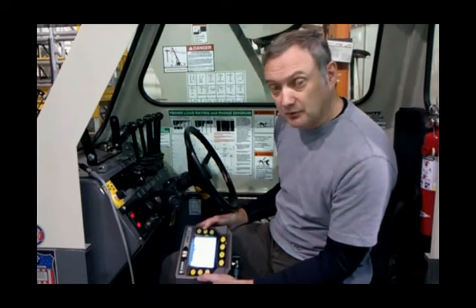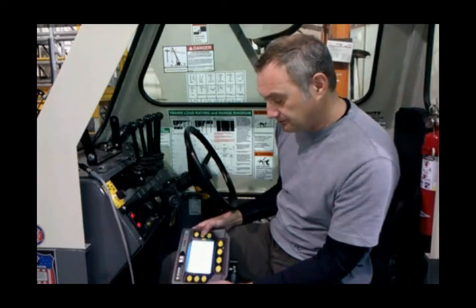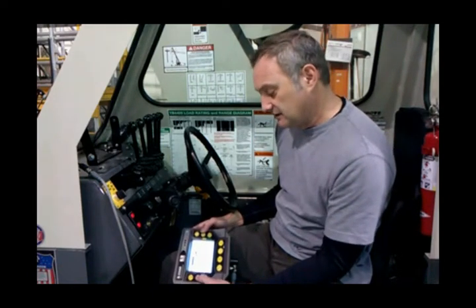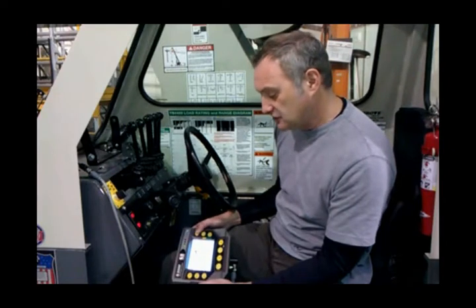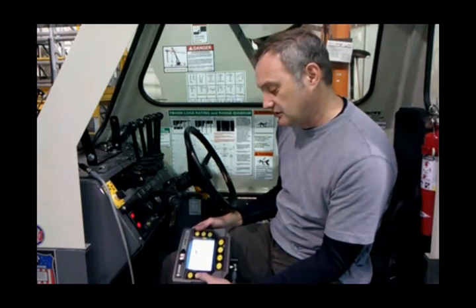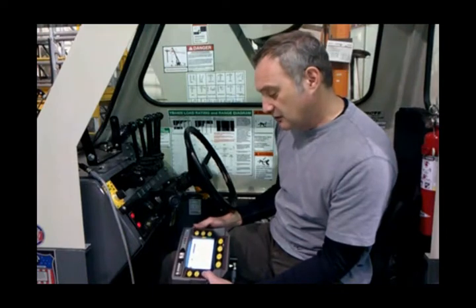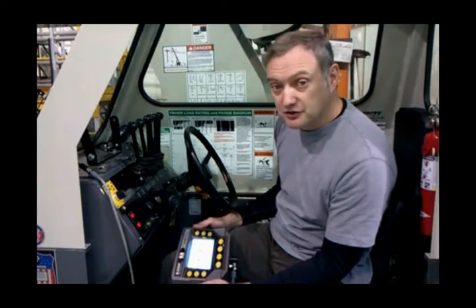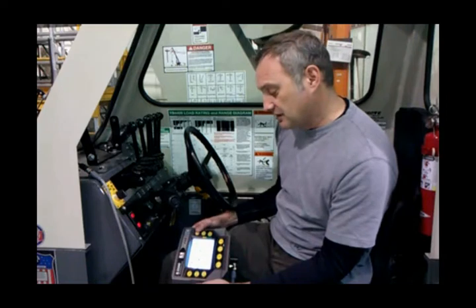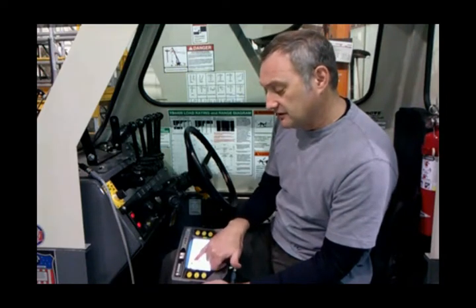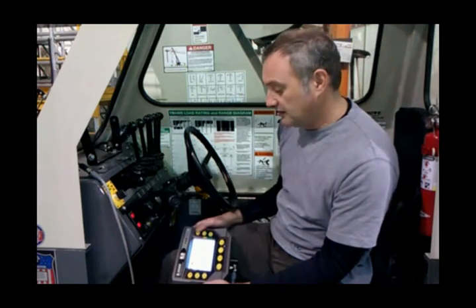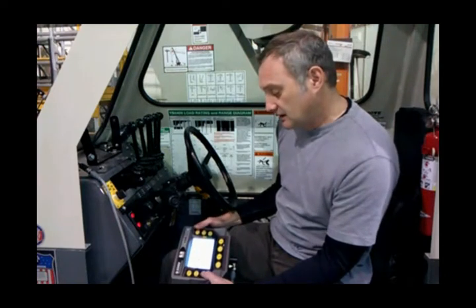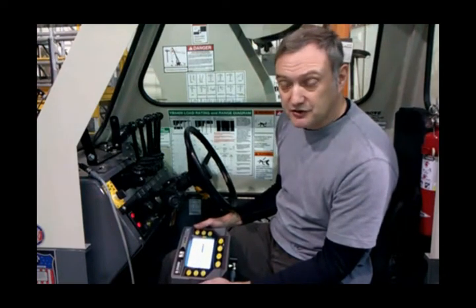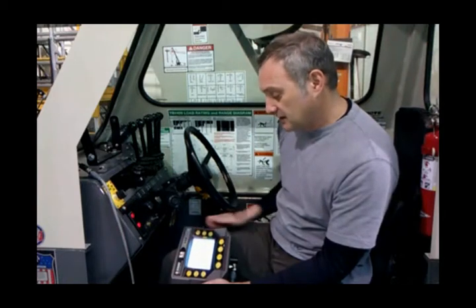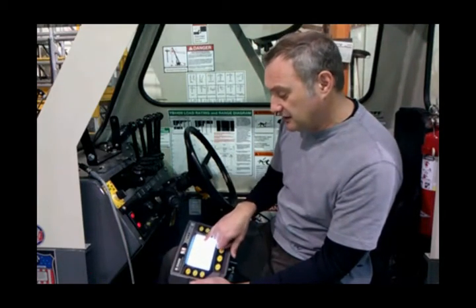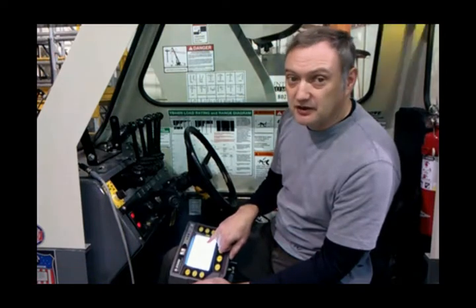So let's go over to the calibration mode. We're going to hit the escape button. Button number 1, highlight calibration, hit the check mark, and enter the password, 1, 2, 3, 4. We're going to scroll down to select pressure transducer and hit the check mark. We're going to make sure that we're on mode 1, which is the bore. We're going to hit the check mark again. And now we're going to drop down to 0 pressure. Hit the check mark. And what we're looking at here is our -2 and a digital value of 304.